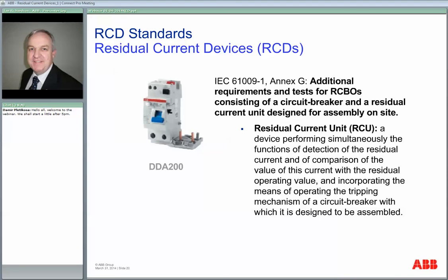One thing to be aware of, the standard requires that once you have assembled these breakers, a breaker onto this RCD, you are not allowed to disassemble it. You have to replace the complete unit. It's a quirky little thing which is built into the standards. So various manufacturers have certain ways of doing it.